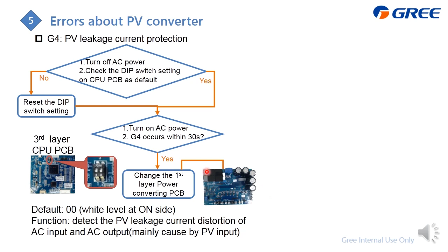Its function is to detect the PV leakage current distortion of AC input and AC output, which is mainly caused by the PV input. Check whether it is the same as default. If it is not, you need to change it to 00. The next step is to turn on the AC power again. If the error occurs again within 30 seconds, that means something is wrong with this first layer power converting PCB. Just replace it.